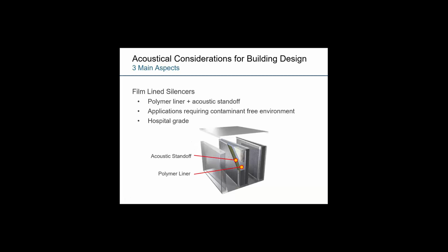Silencers will often also have different types of acoustic medias and media protections depending on the installed area and application. Things like polymer film lining, where the acoustic media is actually encapsulated with a thin polymer film, and this can help provide a contaminant-free environment or prevent any sort of exposed acoustic media within the airstream. And it can be used in a variety of different applications wherever necessary.